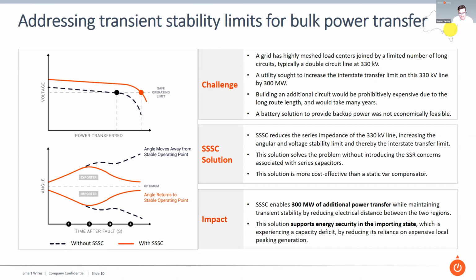So the solution with the SSSC basically reduced the series impedance of the line. It injected a voltage similar to a series capacitor, and cancelled out some of the line inductance, and then pushed out the voltage stability limit. So it pushed out the nose of that power and voltage curve. It solves the problem without the limitations of SSR compared to the series capacitor solution that was proposed. And then also there was an SVC solution proposed for the same problem, and the SSE was more cost effective than that due to the size of the SVC required.